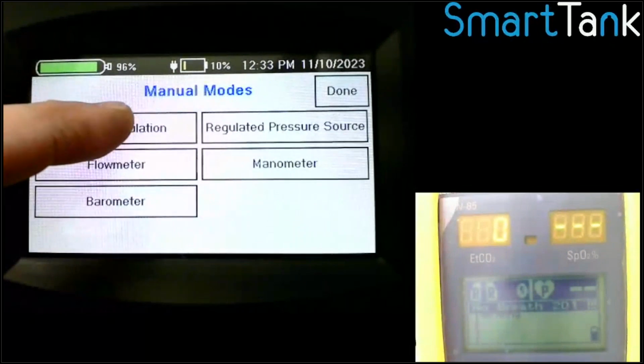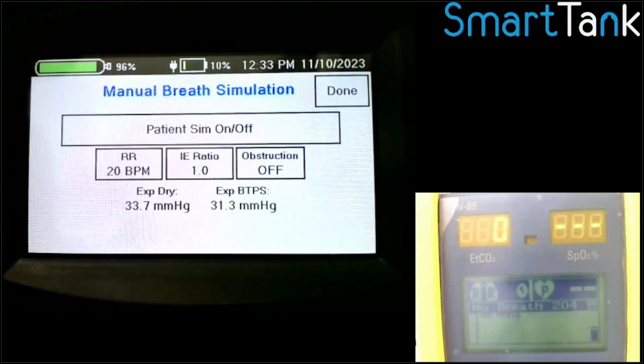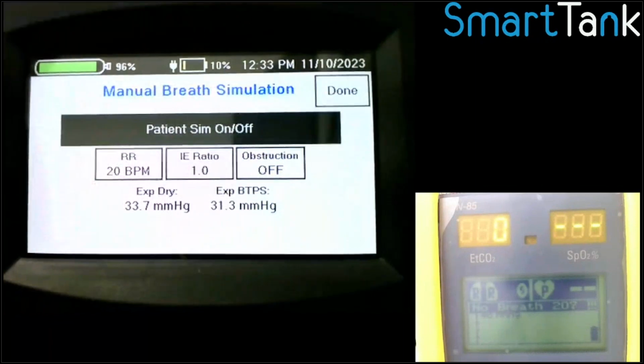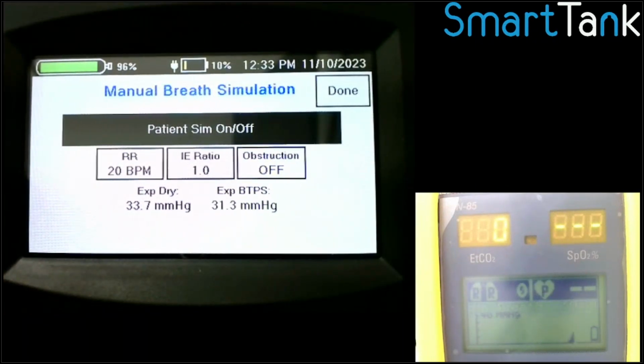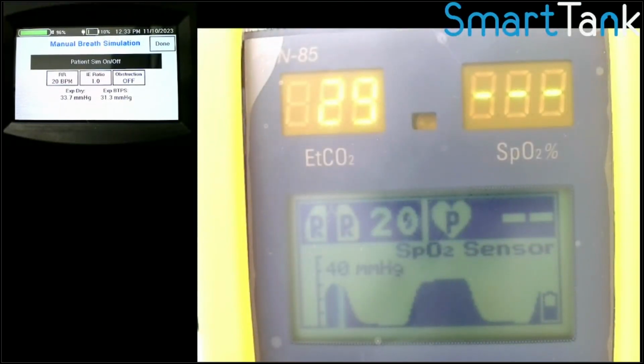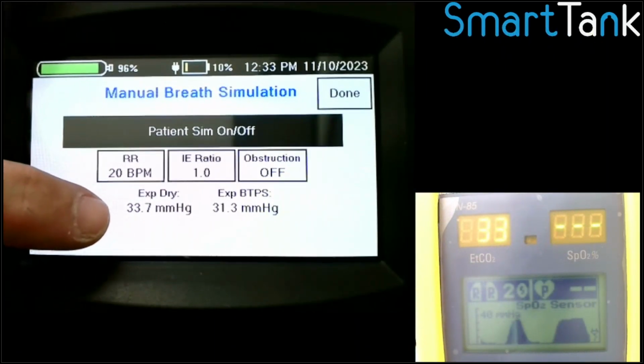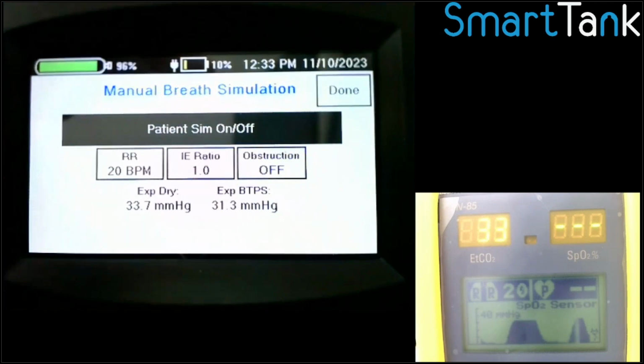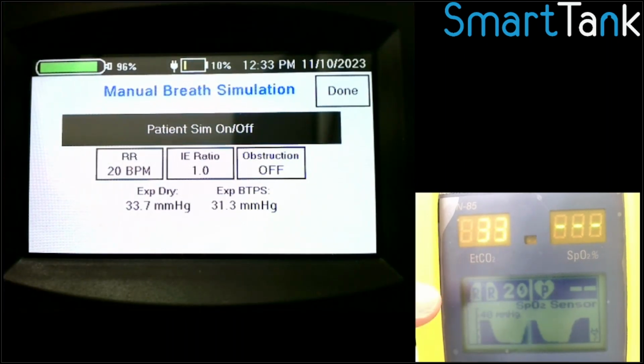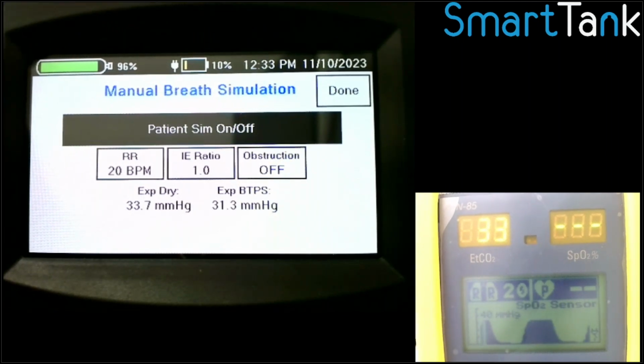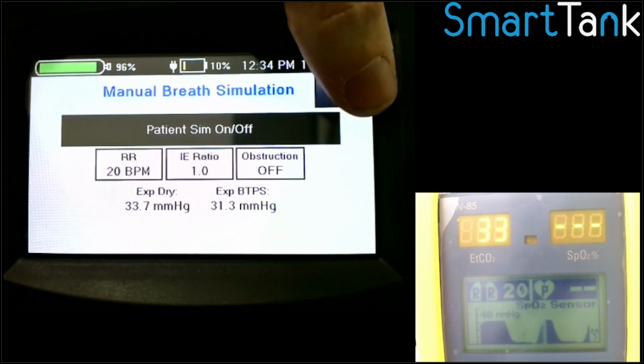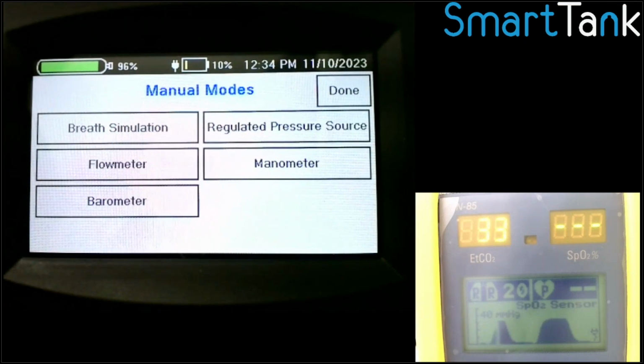And then finally, there's also a breath simulation mode, which a lot of our customers like because they can just spot check devices. But if I turn this on and you watch this yellow screen over here, make that a little bigger, you can see that it's now simulating a patient breath. It's 20 breaths per minute, and it's a 33, which is kind of what's expected. I'll go back. So you can see it's supposed to be 33, and it's reading 33 over on this device right here. And the 20 breaths per minute actually. So you can configure that. So a lot of our customers like that because they can go out. If somebody's like, this isn't working, they can walk out on the floor and just test it real fast and reassure people.